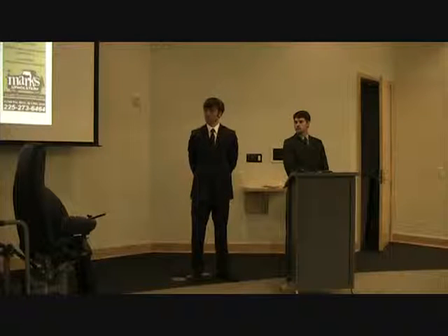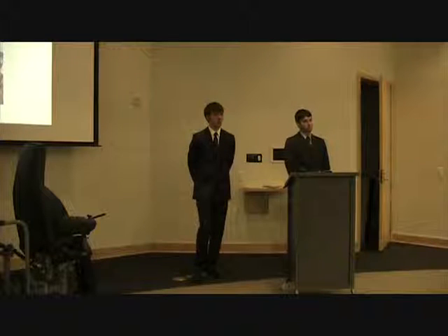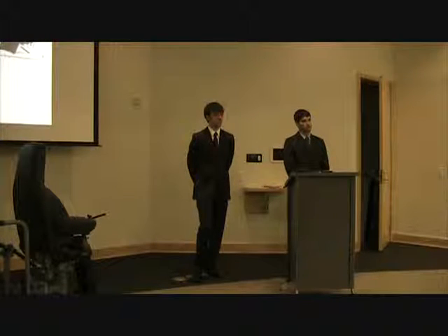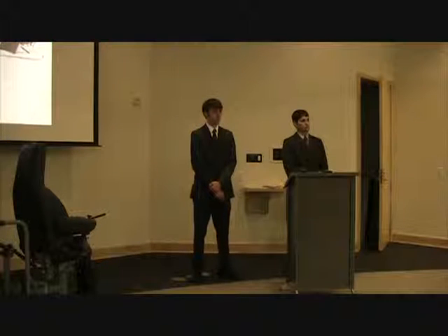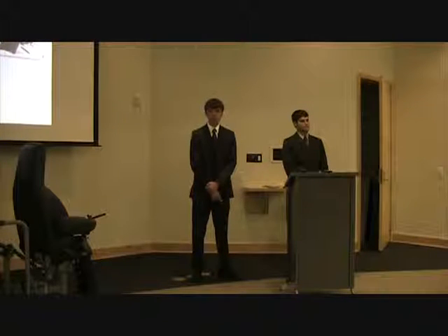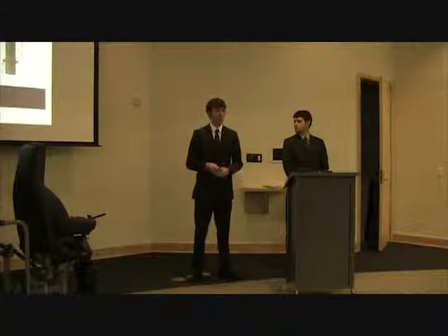Right. What I was saying is that when you did it on a tilt table, as you tilted it over, you changed the direction of gravity. If you've got 150 pounds in the chair and I try to push you over with a lateral force, I don't change the direction of gravity. And so you get the peak moment at the bottom. So the question I'm asking is, have you run the numbers on how much moment that joint can take? I think the amount of moment it can take was during the basic analysis, when it was straight. When it was tipping, no, we didn't do that.